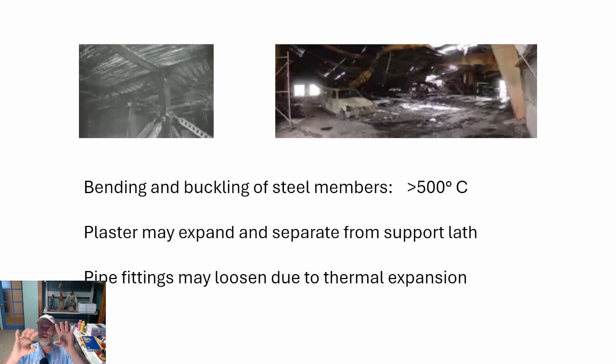So if you're surrounding steel by heavy black upper layer smoke from a fire, the steel actually very closely follows the temperature changes in that smoke. And the reason for that is the coefficient of conduction for steel is about 45.8 watts per meter Kelvin, I think is what the units are on that.